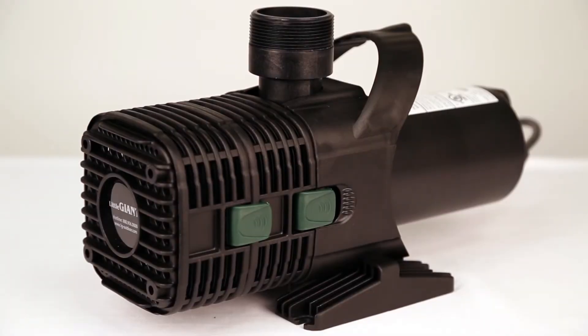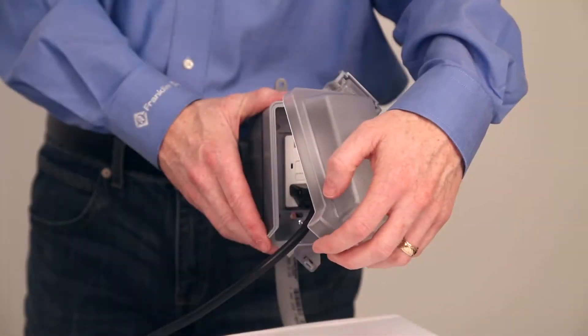We are here to show you how to maintenance your volute and impeller on the Little Giant F-Series pumps. This should help if you are experiencing flow reduction, no flow at all, or hearing a loud noise. For maximum performance, we recommend doing this at least once a year.